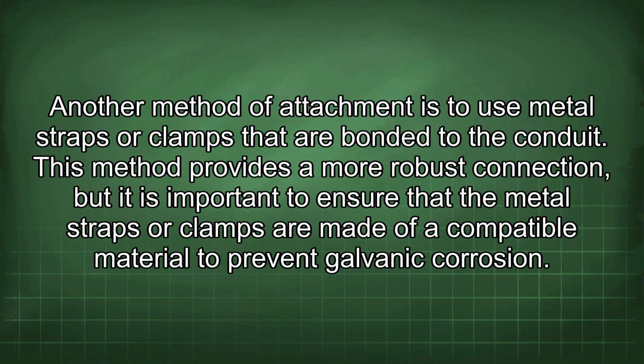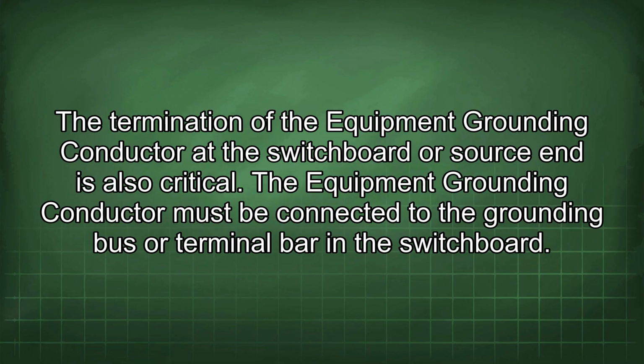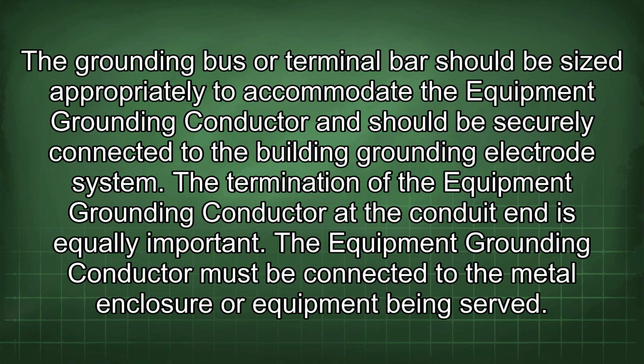Another method of attachment is to use metal straps or clamps that are bonded to the conduit. This method provides a more robust connection, but it is important to ensure that the metal straps or clamps are made of a compatible material to prevent galvanic corrosion. The termination of the equipment grounding conductor at the switchboard or source end is also critical. The equipment grounding conductor must be connected to the grounding bus or terminal bar in the switchboard. The grounding bus or terminal bar should be sized appropriately to accommodate the equipment grounding conductor and should be securely connected to the building grounding electrode system.